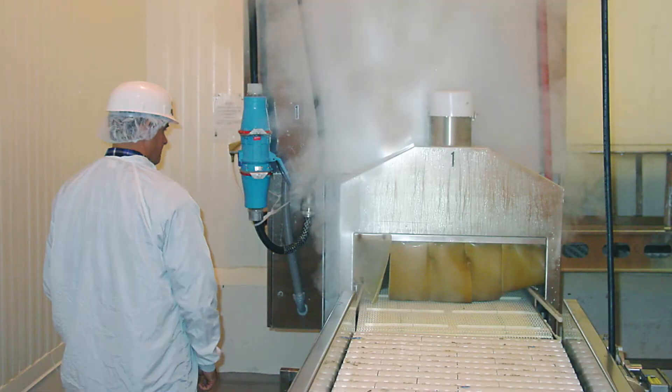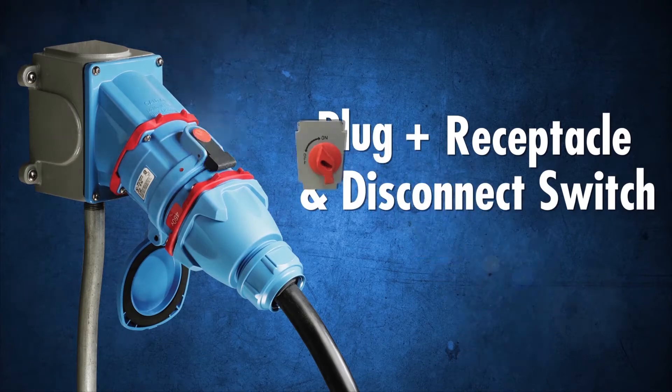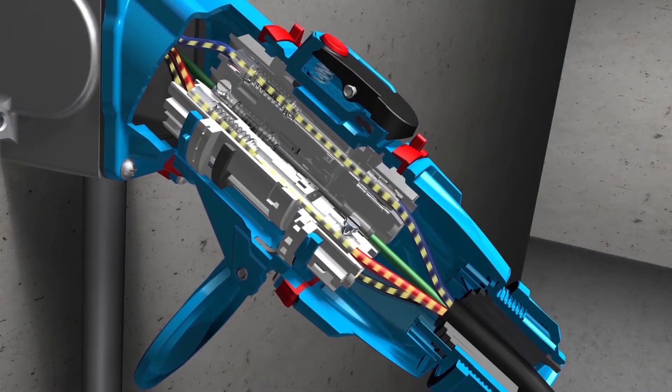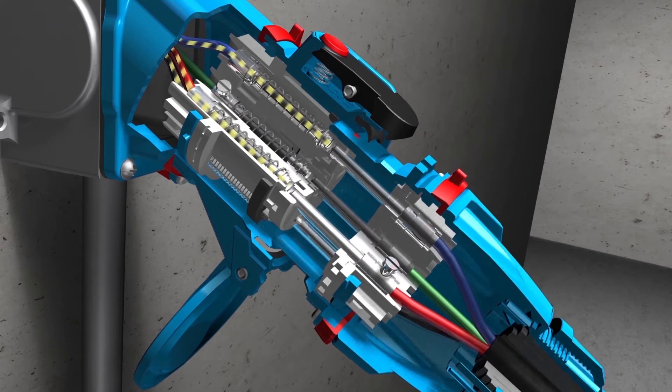Meltric switch rated plugs and receptacles are a combination plug, receptacle, and disconnect switch in the same device. An integral switch mechanism inside the receptacle safely de-energizes the plug before an operator can withdraw it.